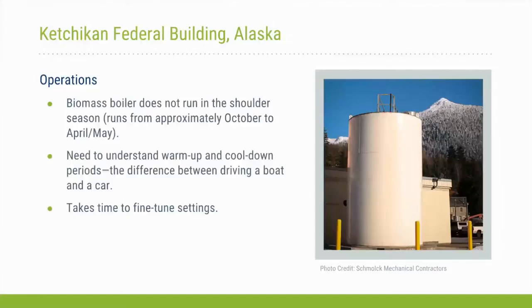So as you can see from this one, the biomass boiler doesn't run in the shoulder seasons. It needs outside air temperatures to be consistently below about 45-50 degrees to operate efficiently. And as Marty was saying, you have to practice a little patience with the system as the warm-up and cool-down periods do take longer than with an oil fire boiler. For warm-up, from the time the biomass boiler is programmed to start bringing the building up to temperature versus if you were using an oil fire boiler, it does take longer for the biomass boiler to come up to temp and heat the loop. This isn't problematic, but it's just something that you have to be aware of, especially when you're programming your building automated system. The same is true for cool down periods. The pellet fuel, once it's fed into the system, it has to be burned before the system can actually start cooling down.